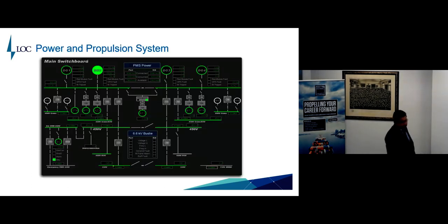This is a power system. There you can see a lot of components. Most of you can identify these two. The basic power and propulsion system. A little bit more talk about this. There are two sections of switchboard, four generators, two in this one, each side, and then you have six thrusters: 1, 2, 3, 4, 5, 6. Six thrusters, and this generator is a basic switchboard. I will talk about those things a little bit. Now you can see that there's a bus tie between the two sections, this close, and there's a thruster. VT1 can be fed from this side or this side, port or starboard, or A or B, whatever you call it, right? And then you can see the green light, green indication in this system. But the indication shows open, which is not correct actually.